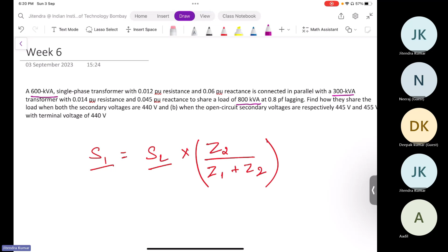My guess is that the second transformer will get overloaded, because it has a much lower kVA rating, exactly half of the first transformer. If you simply add 600 plus 300 kVA, it becomes 900, and our load is 800. When they reach equally 300 and 300, it can cater 600. We will see the formula for what happens in such cases: what is the maximum load kVA that could be catered from both transformers without getting overloaded. Do not get worried, we will solve this and you will get acquainted with these concepts.